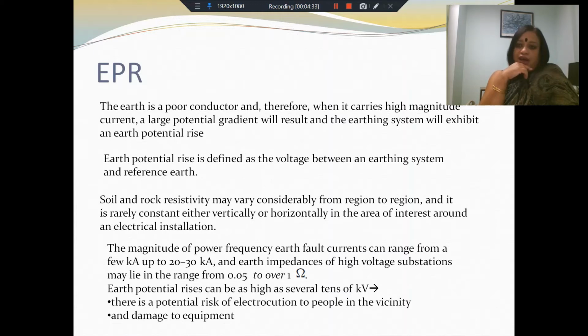So you will have an earth potential rise at a particular point. Say there is a reference earth, a point which is definitely earthed, and between that point and another point you have a very high IR. The second point will rise to a very high potential compared to the reference earth, and this is called earth potential rise. Earth potential rise is defined as the voltage between an earthing system and reference earth. You may imagine that under normal conditions this voltage should be 0 or very close to 0, because both are parts of the same earthing system. But under abnormal conditions, even points on the earthing system can rise to very high potentials with respect to the reference earth. And this potential value is called the earth potential rise, or EPR.